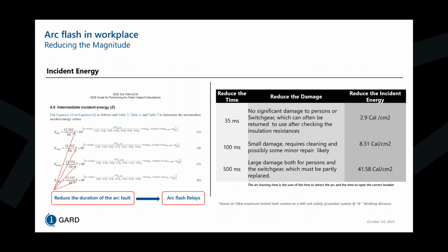So this is based on a 50 kA maximum bolted fault current on a 480 volt solidly grounded system at 18 inches of working distance. And the arc burning time is the sum of the time to detect the arc and the time to open the correct breaker.